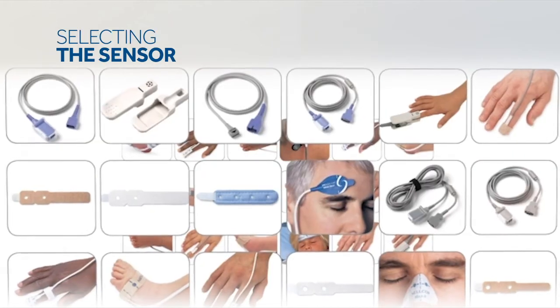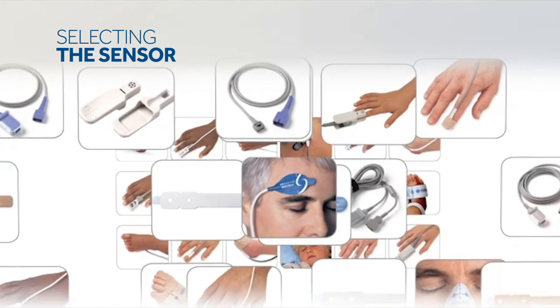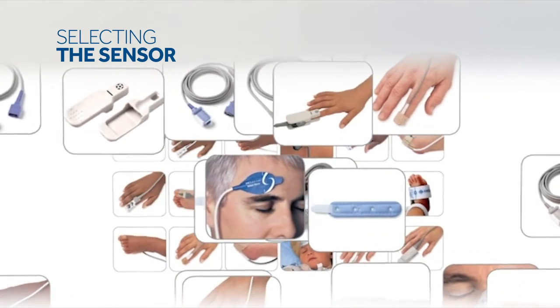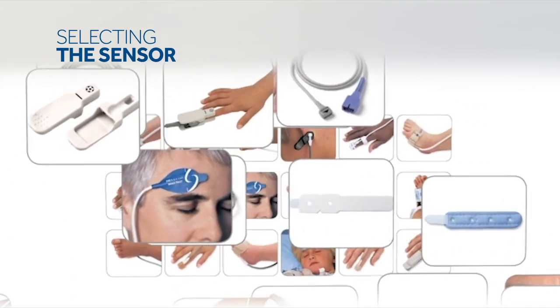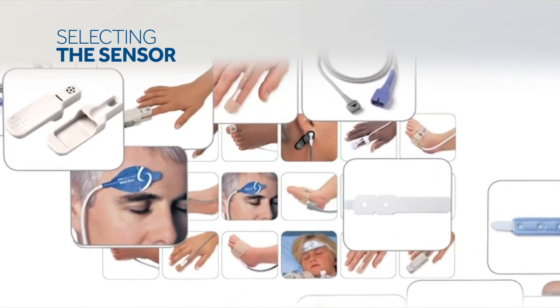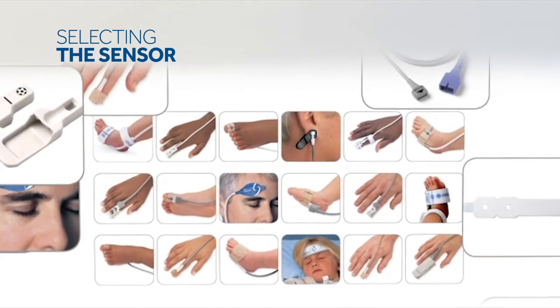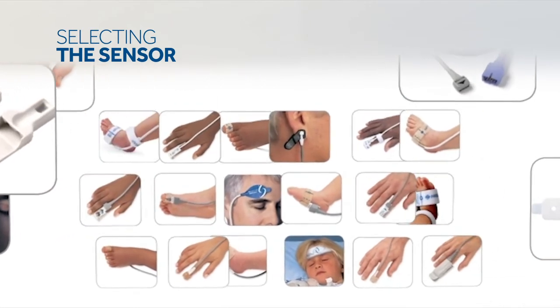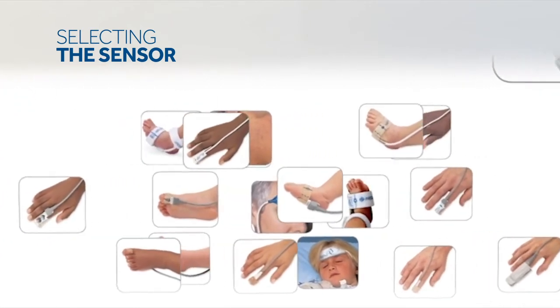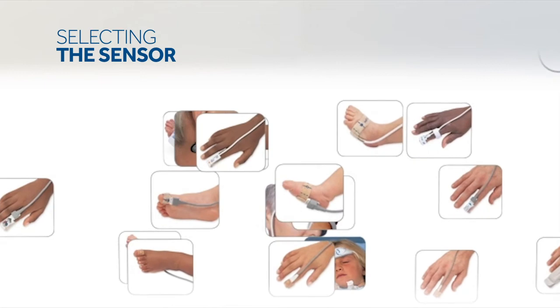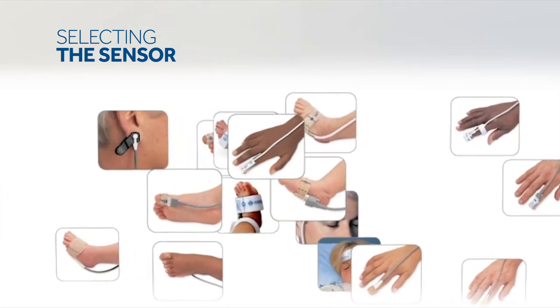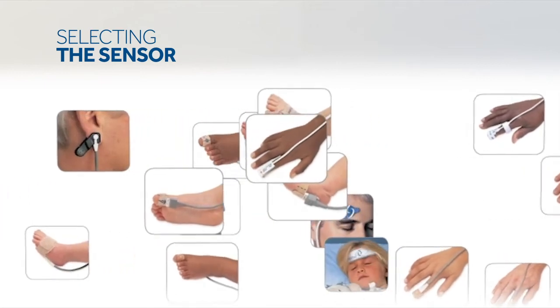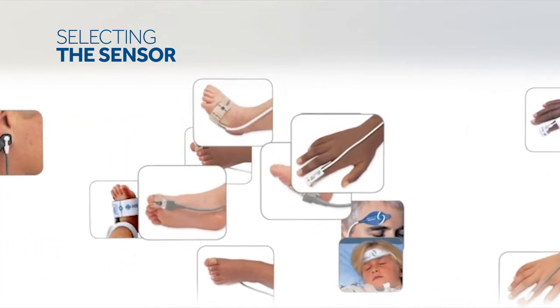Select a compatible Nellcor pulse oximetry sensor for the patient and desired application. When selecting a sensor, consider the patient's weight and activity level, adequacy of perfusion, availability of sensor sites, need for sterility and anticipated duration of monitoring.